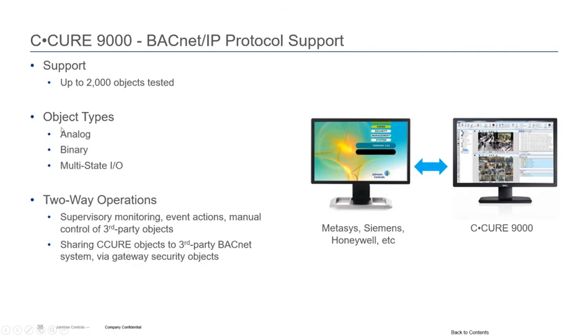We do support not all, but the most common object types. And we are in the process of upgrading the internal polling mechanisms. Right now, we're publishing that up to 2,000 BACnet objects can be shared. And you might think that's a lot, but some jobs have already exceeded that. So we are in the midst of a nice enhancement to the BACnet driver.